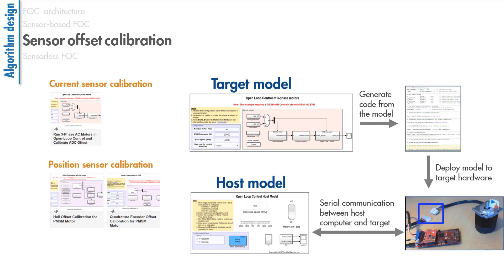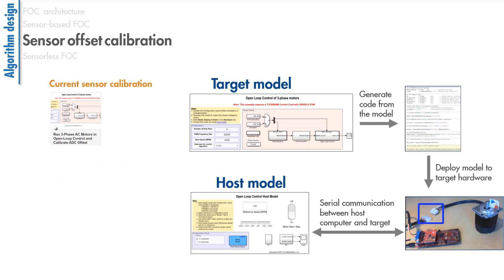Let's discuss current sensor calibration briefly. Phase currents are measured using analog-to-digital converters or ADCs. In order to find the ADC offsets, we need to read the ADC counts when there are no phase currents in the motor. That's why the motor is disconnected from the inverter.